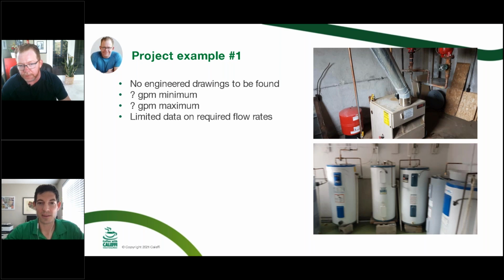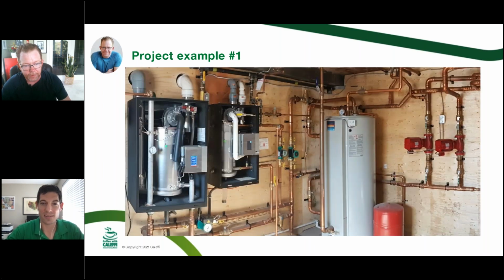So this job in particular, once everything was right-sized and selected, this is what it looked like when it was installed. So this ended up being 2 SL boilers by IBC. One's a 399, one's a 115, right-sized, so we get a really deep, good modulation on it. And in this case, it's tied to a Thermomax. So the sizing with this was done using the IAPMO calculator, which Max is going to talk a little bit about here in a minute.